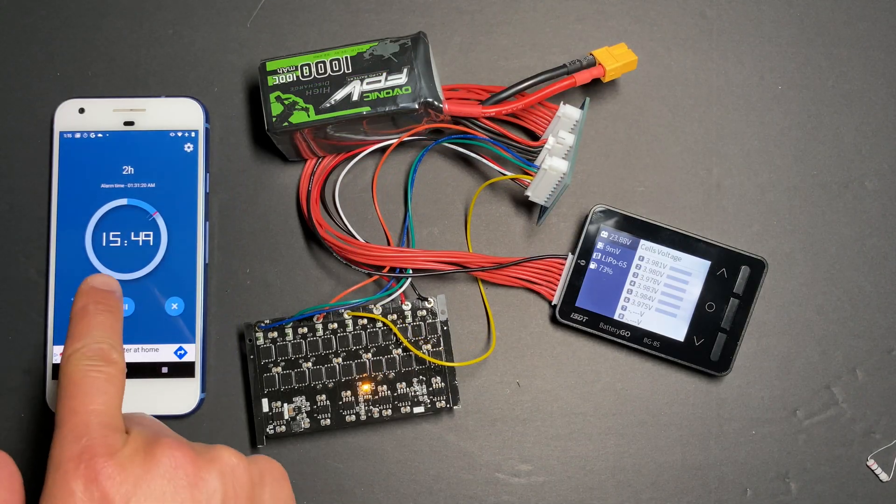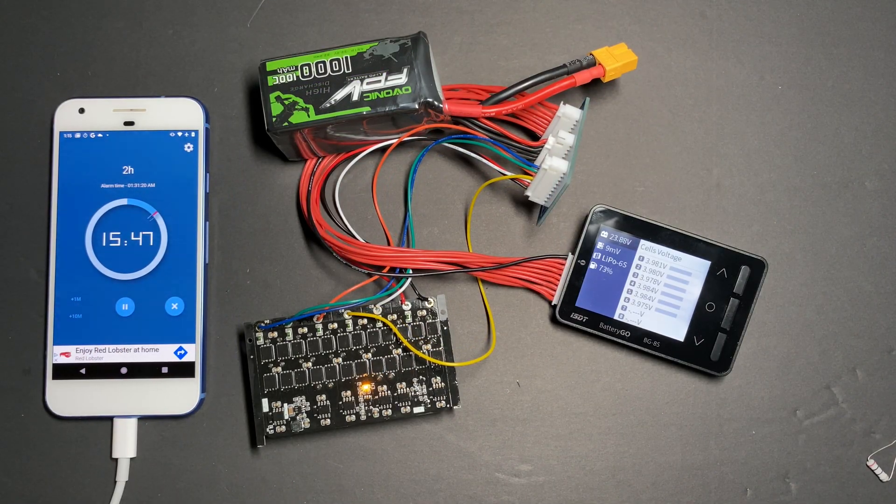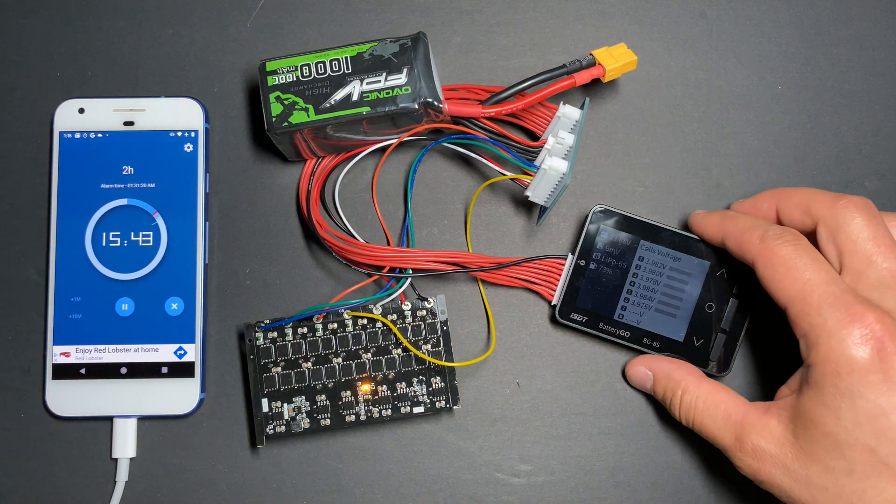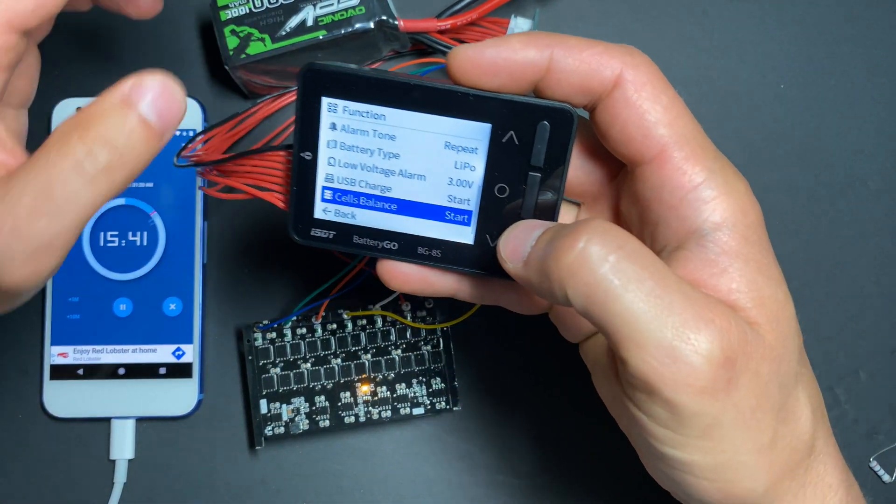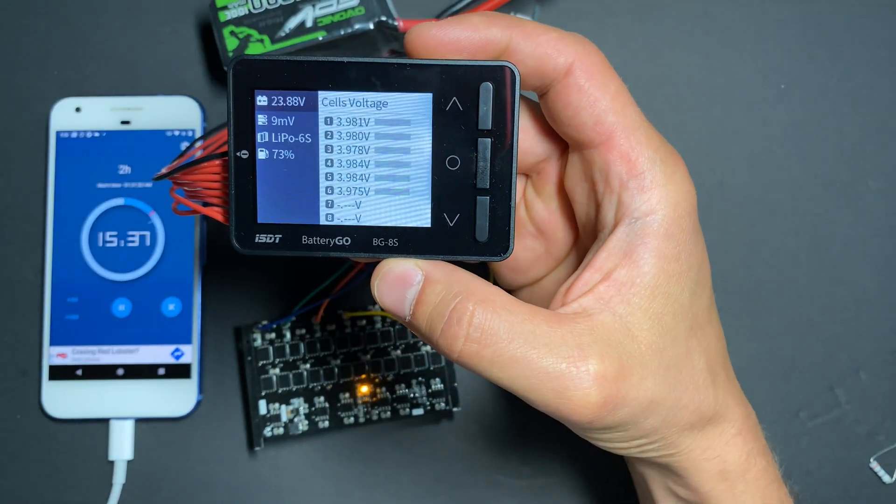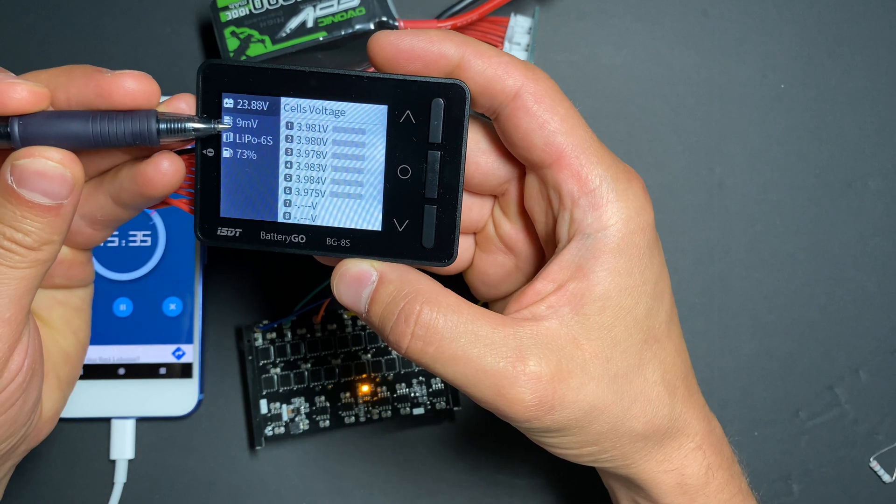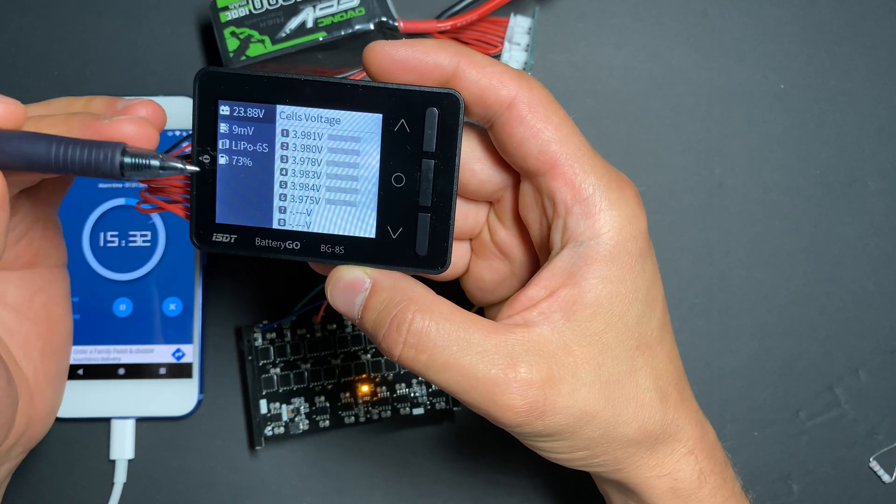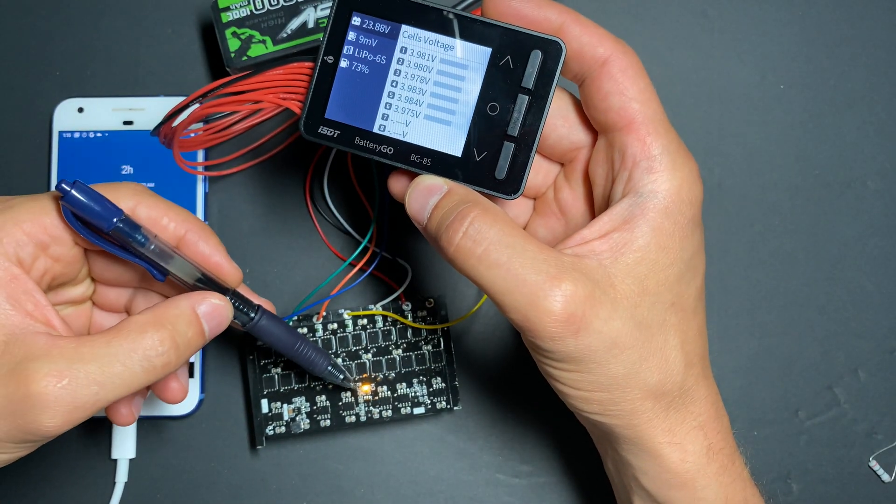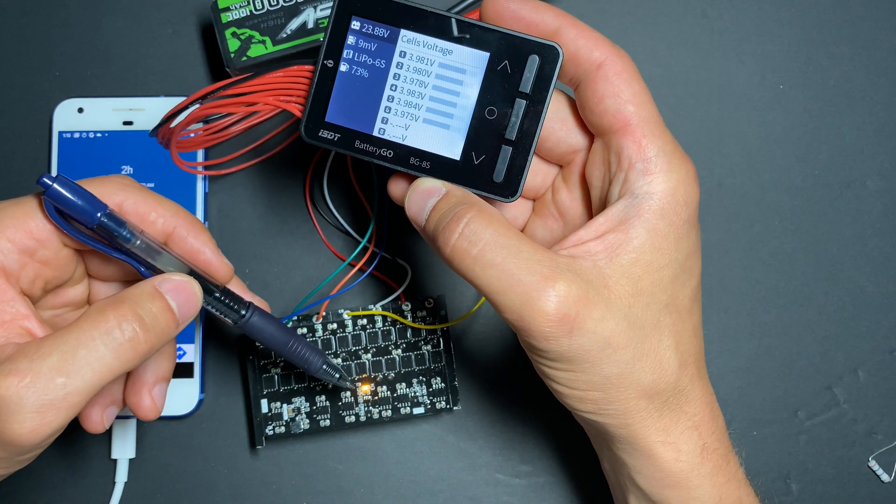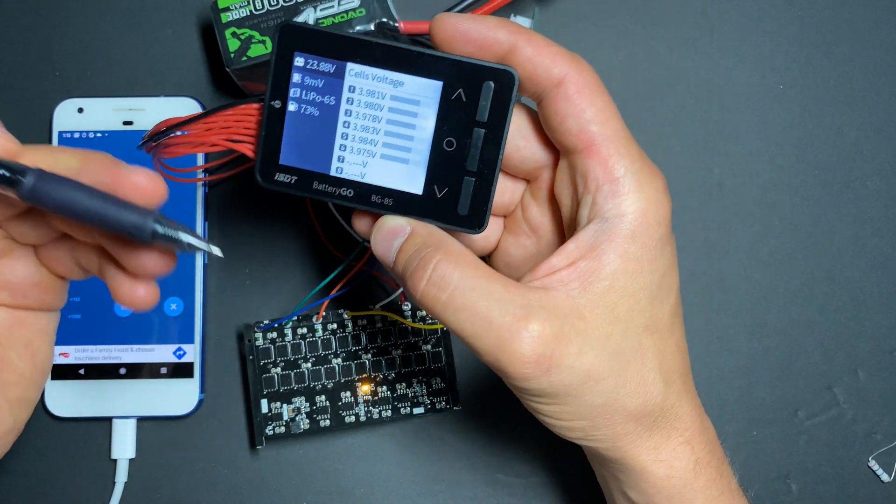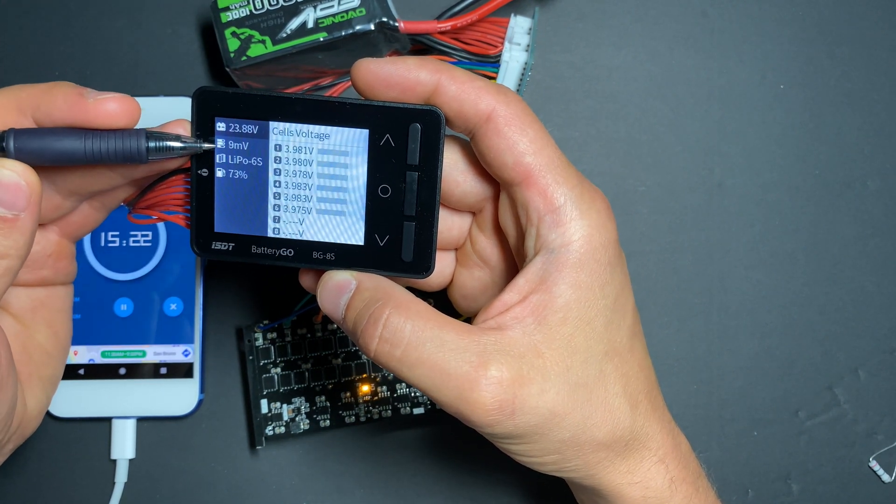We are 16 minutes left till balancing will end, but I will stop this test number one because if we see the cell difference right now, we are at nine millivolts cell difference. So all cells are equalized. Even though we have this indicator showing it's still working, still balancing, but nine or eight, it was just eight millivolts. It's a great result.